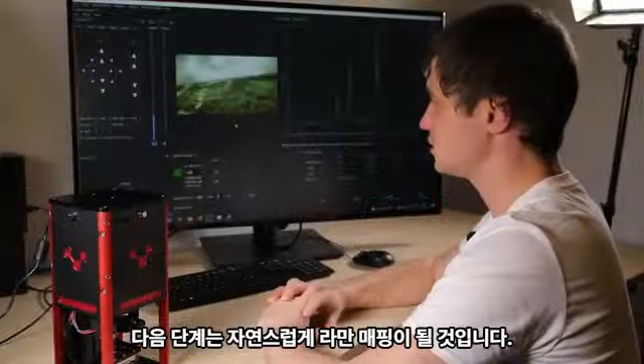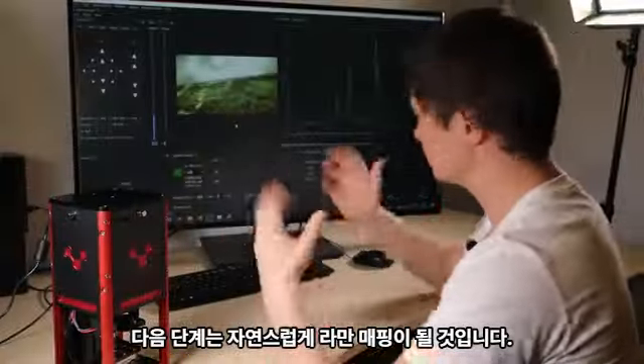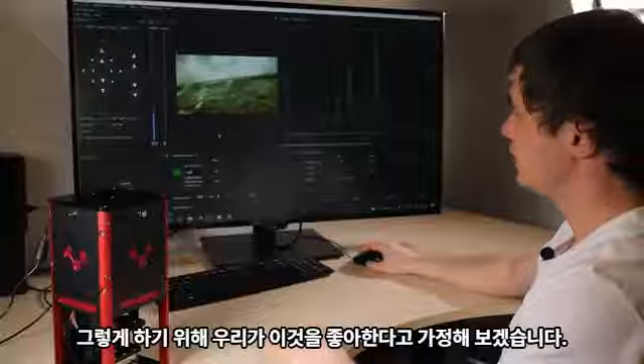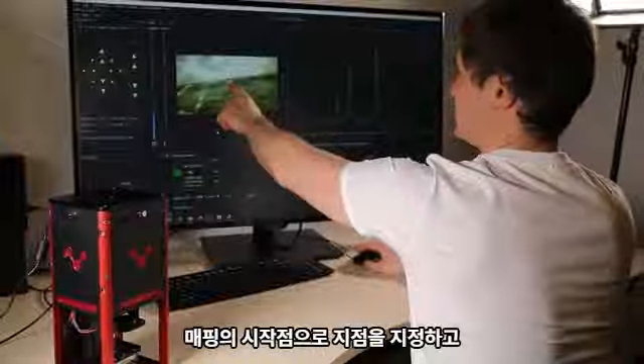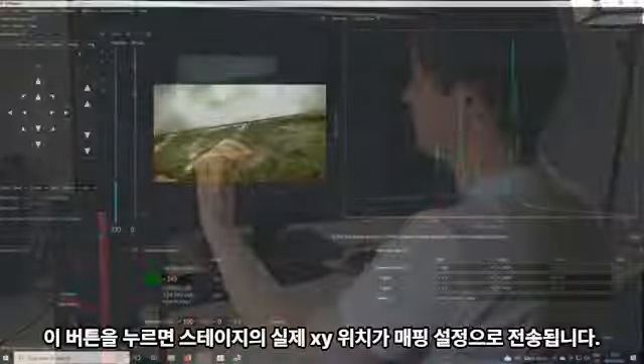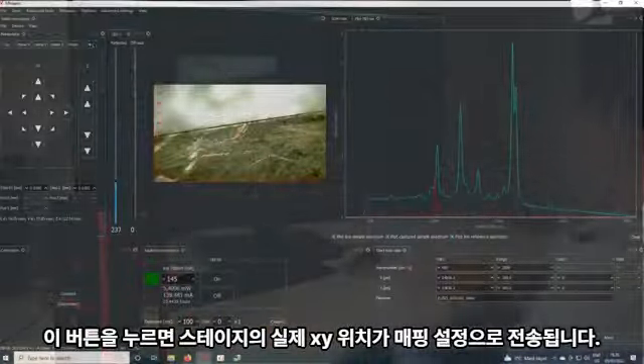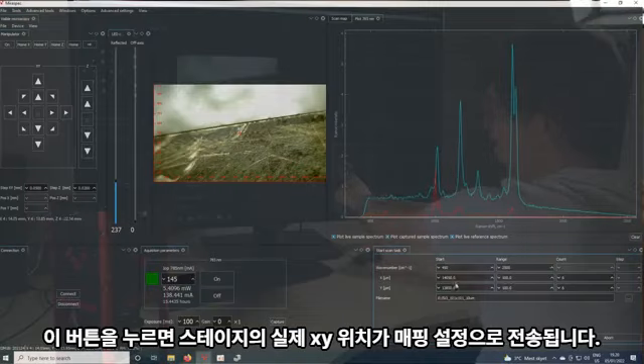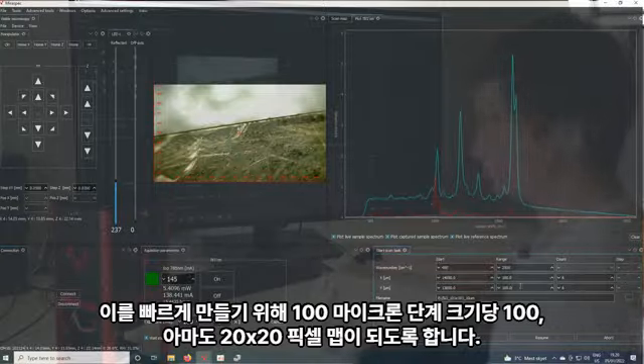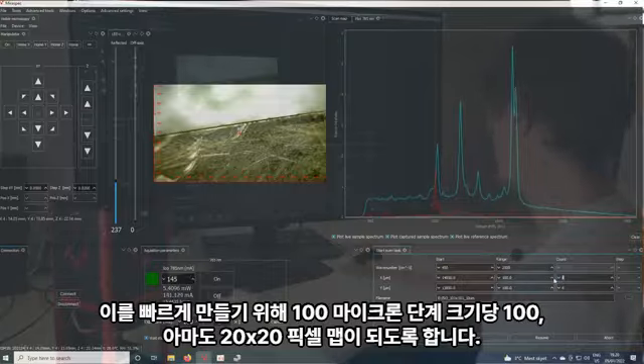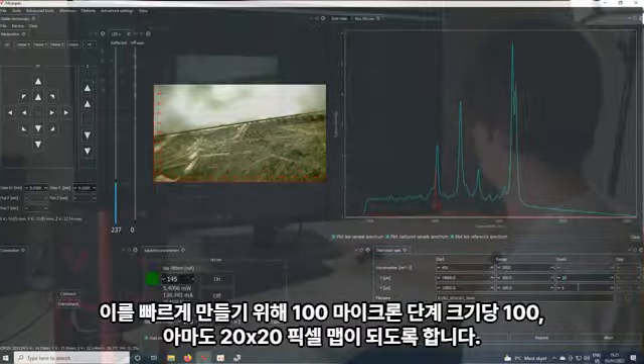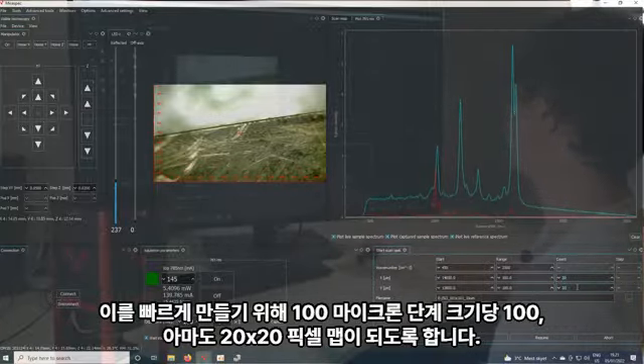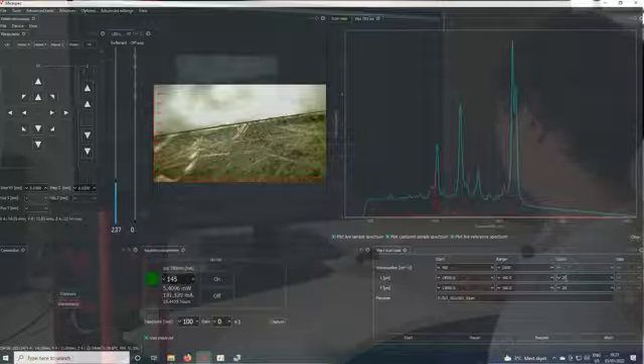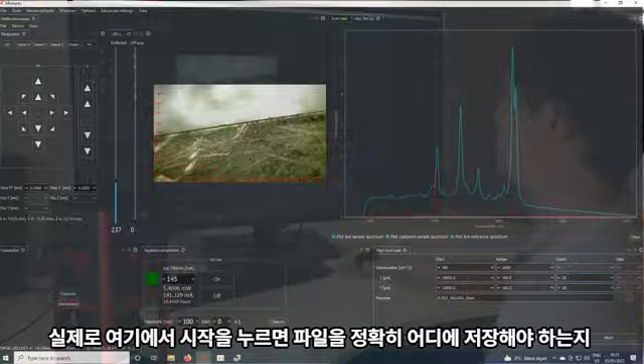The next step for us would naturally be Raman mapping. In order to do that, let's say we like this point as a starting point for the mapping, and I press this button and it transfers the actual XY position of the stage into the mapping settings. Let it be 100 by 100 micron step size and probably a 20 by 20 pixel map, in order to make it fast. And I press start.